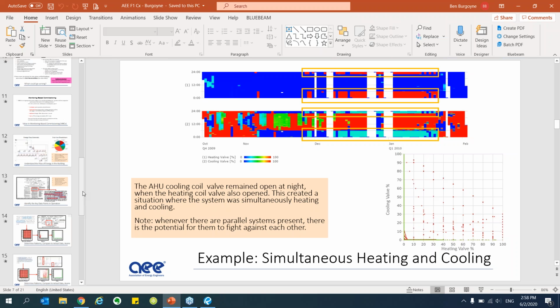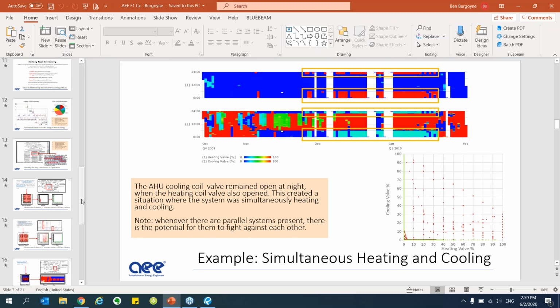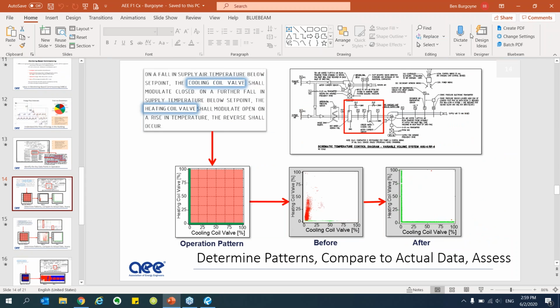Thank you. We have time for about one or two more questions. The next question is, how would the humidity levels change if both the heating and cooling coils are not supposed to work together? Let's see. Well, it depends. I want to look at the schematic I have here for heating and cooling together. It depends on which comes first, the hot water coil or the cooling coil. And what we have here is the hot water coil before the cooling coil.